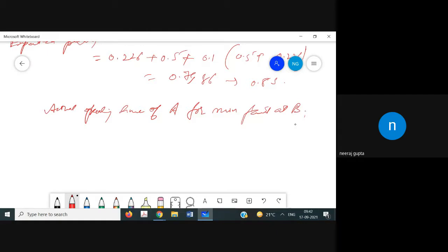So as we know, the minimum fault current is 2000 ampere. For relay A, the CT ratio is 300 to 1. So the relay current is 2000 divided by 300, which equals 6.66 ampere.